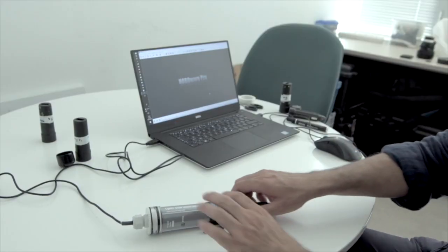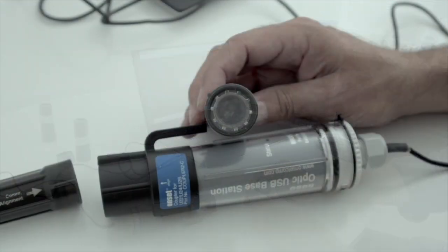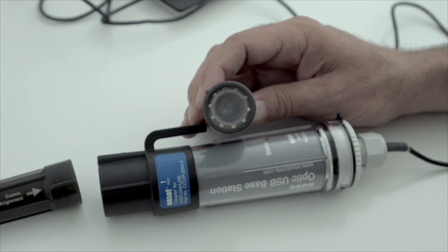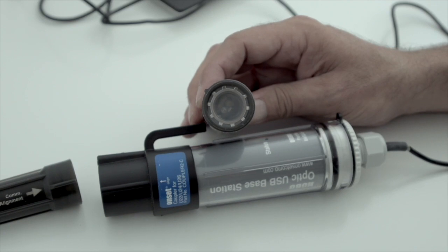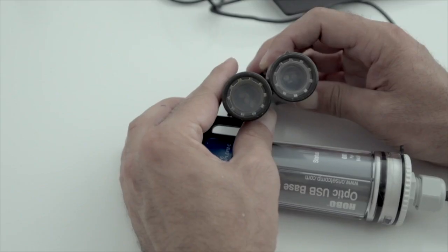In case of doubt, you can check directly from the data logger if it has been correctly launched by looking through the optical window. You should see through the optical window of the Hobo U22 a small red light blink. A well-initialized data logger blinks a red light once every 8 seconds, as you can see in the video, meaning that it was launched in delayed start mode. A currently logging logger blinks at a faster rate.